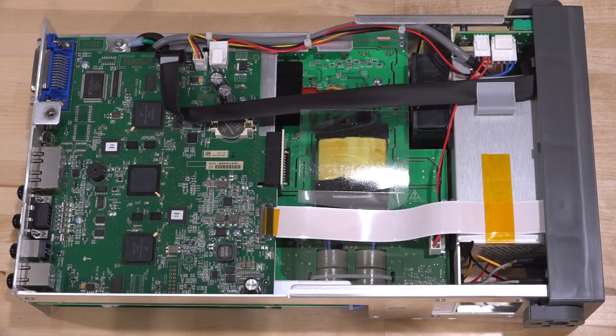So let's take a quick look inside this instrument and consider some of the design challenges. Now, this is a high voltage instrument. Creating a high voltage power supply inherently is really not that difficult, but to create one that has low ripple becomes much harder, especially with the precision of, let's say, a 6.5 digit meter that would be accompanied with it.